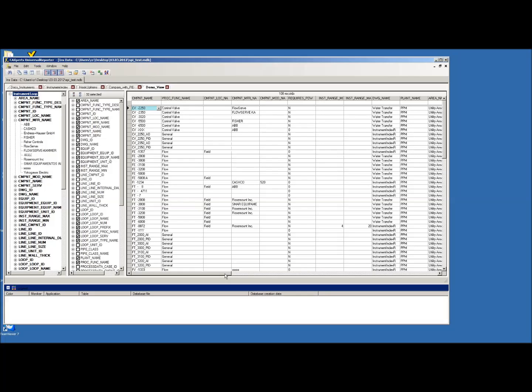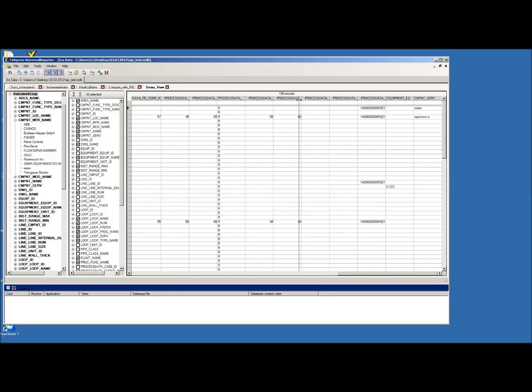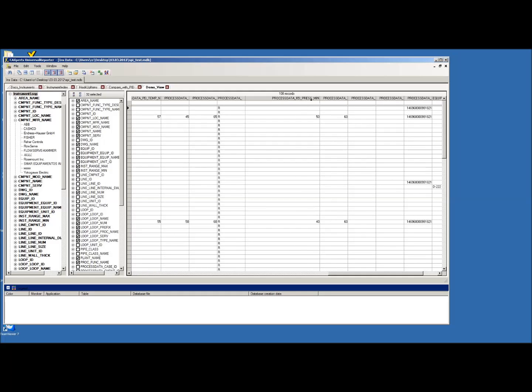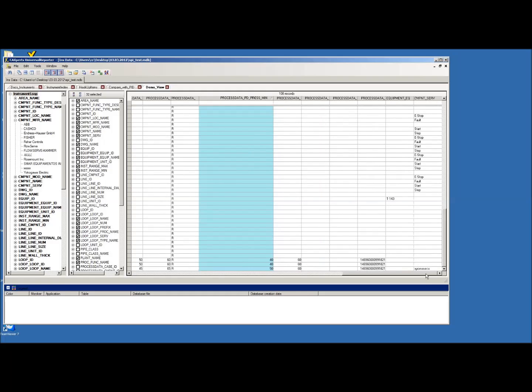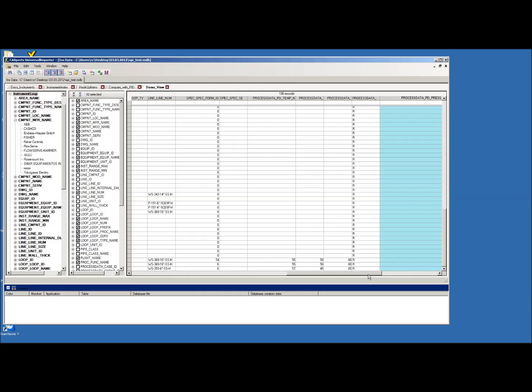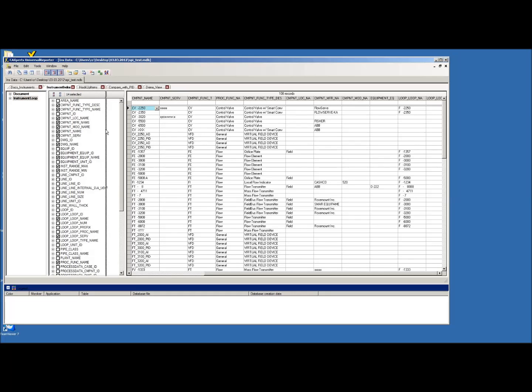Before leaving the general topic and moving to the instrument index, I want to show that we don't only see data coming from the instrumentation table — we also have data coming from process data on the back side, such as minimum pressure and so on. These can also be used for sorting, filtering, or whatever you want. It's a combination from many different tables from SPI. The next topic is how to generate an instrument index. I have defined a special view called 'instrument index' which only displays instrument loop data and document data, and from this view I can generate an Excel report.